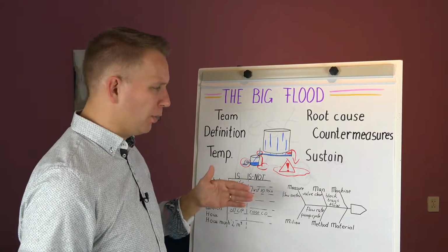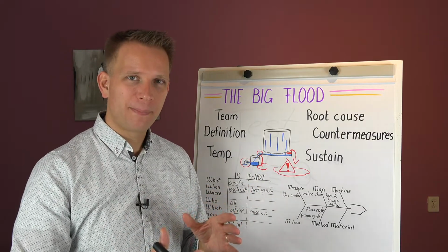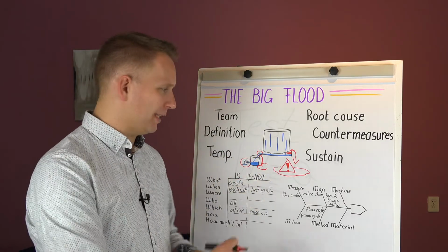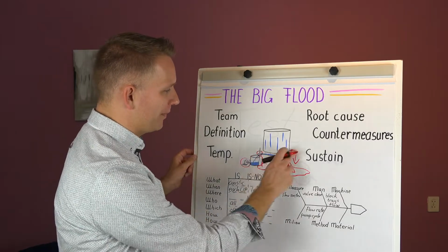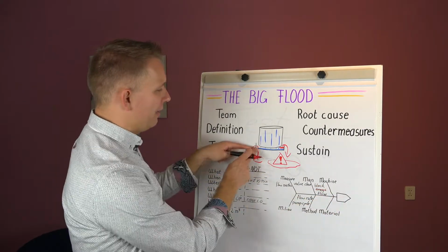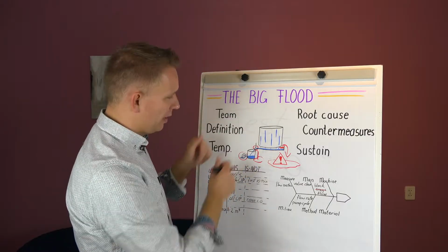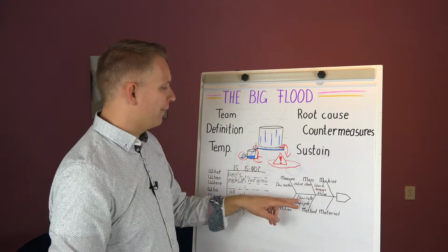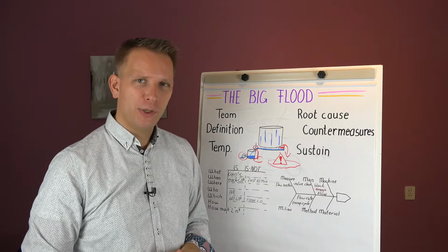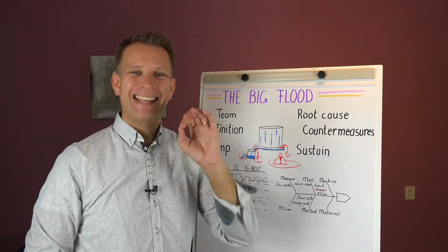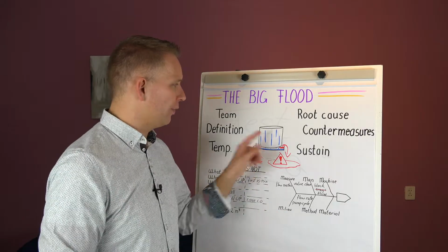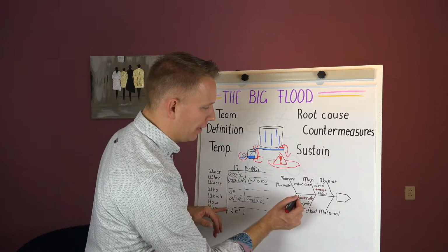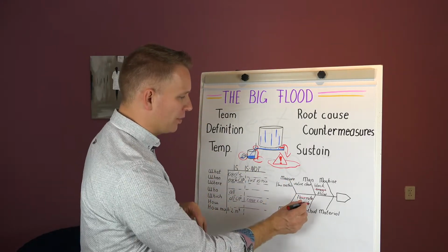Maybe the valves are closed or the pump is not steered correctly. And when we kept analyzing all of these points through a number of cleaning cycles, what we saw is that the tray is basically okay if this one is wide enough. By this time we installed a wider exit, then it did overflow a lot more in this small vessel. The flow rates, yes, but honestly, this pump could easily pump away the flow rate we are putting in as cleaning. So it helped a bit, but that wasn't the one. And also how it started pumping, that was okay.